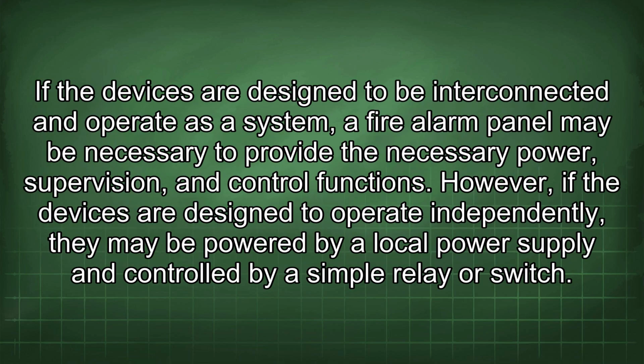Sixthly, the specific wiring and interconnection requirements for the duct detectors and horn strobes must be carefully considered. If the devices are designed to be interconnected and operate as a system, a fire alarm panel may be necessary to provide the necessary power, supervision, and control functions. However, if the devices are designed to operate independently, they may be powered by a local power supply and controlled by a simple relay or switch.